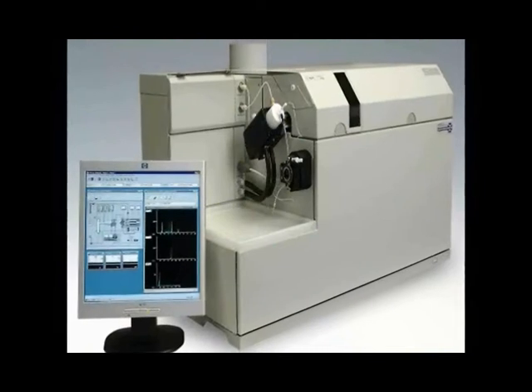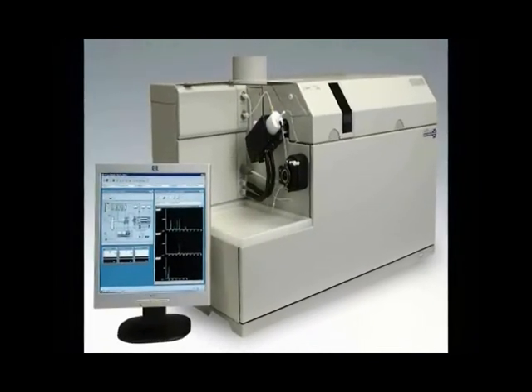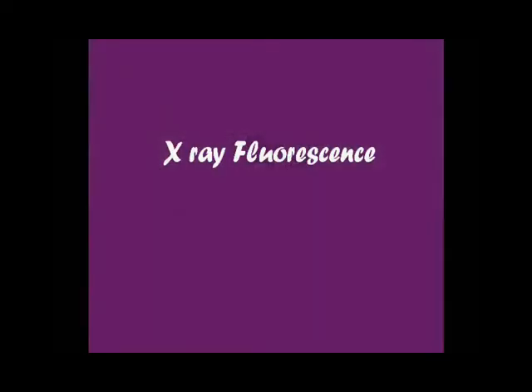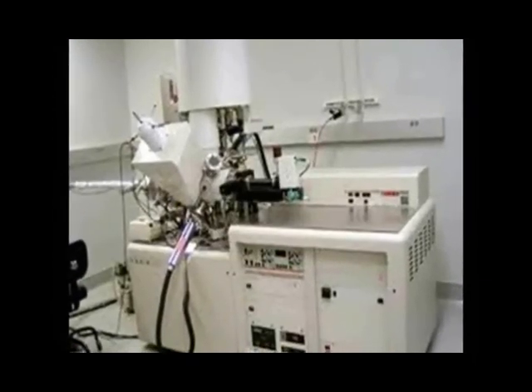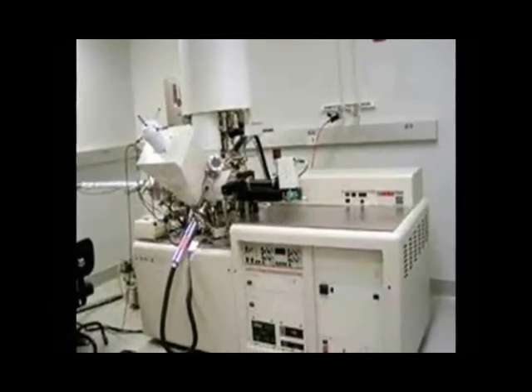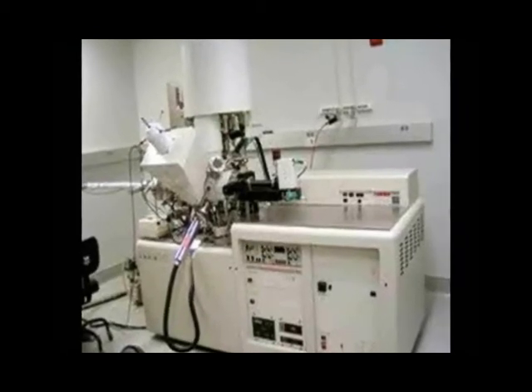Inductively coupled plasma mass spectroscopy ICP-MS detects ions on the basis of charge-to-mass ratio. X-ray fluorescence is based on the principle of emission of secondary or fluorescent X-rays from atoms that have been excited by absorption of high-energy X-rays or gamma rays.